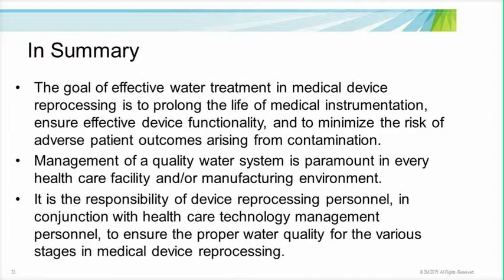For most attributes, with some exceptions, we're talking about the handheld test kits, something like what facilities would do. It's very common to have test kits for total dissolved solids and chlorine content, typically measured right by your water system by your facilities personnel. Test kits for microbial, conductivity, and TOC are not as common. Nelson Labs does provide the sampler containers as well as the testing for that. But again, those quick test kits, the rapid readouts, are not readily available for on-site use.